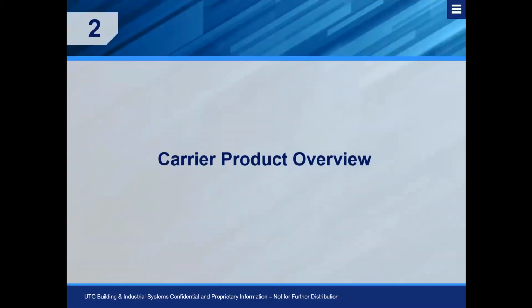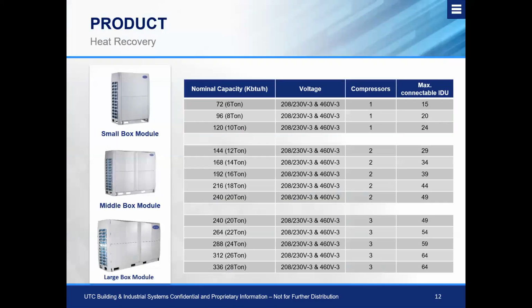All right, so let's go ahead and take a look at the carrier product overview. With the heat recovery side of things, which is going to be that simultaneous mode, we have a unique advantage with this configuration of outdoor units. You can see here we refer to these boxes as modules because they offer a single base rail capability, which means we do not require twinning kits as we start increasing certain tonnages. For example, if we were to look at the Toshiba carrier system, when we go to 16 tons on that system, we have 2 units twinned together to equal that capacity, 2 8-ton units.